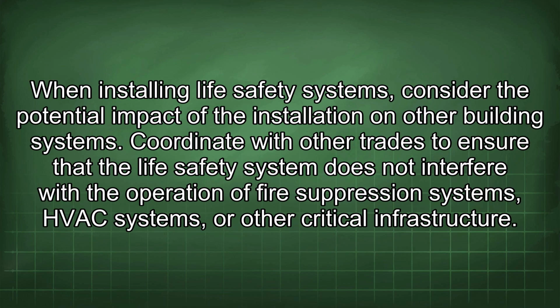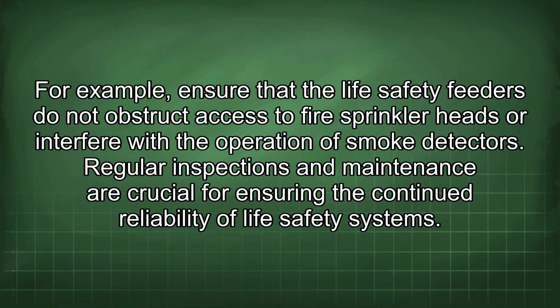When installing life safety systems, consider the potential impact of the installation on other building systems. Coordinate with other trades to ensure that the life safety system does not interfere with the operation of fire suppression systems, HVAC systems, or other critical infrastructure. For example, ensure that the life safety feeders do not obstruct access to fire sprinkler heads or interfere with the operation of smoke detectors.